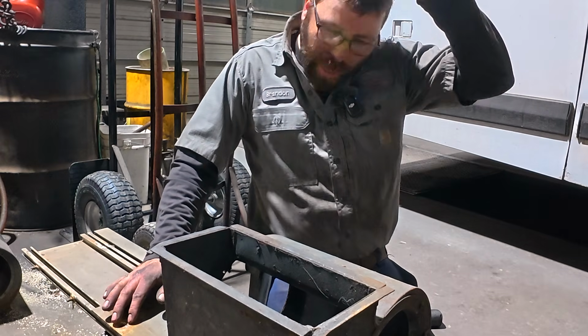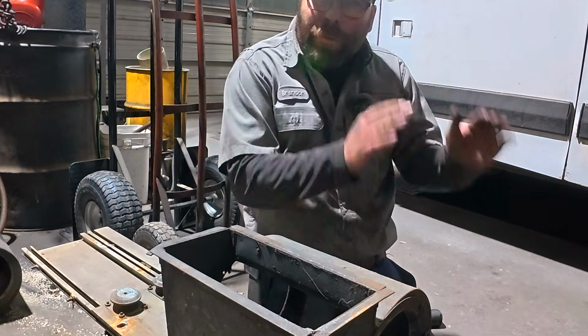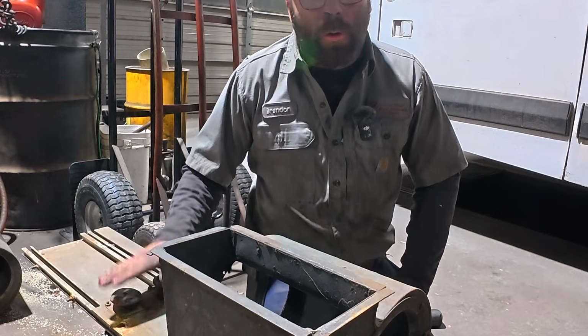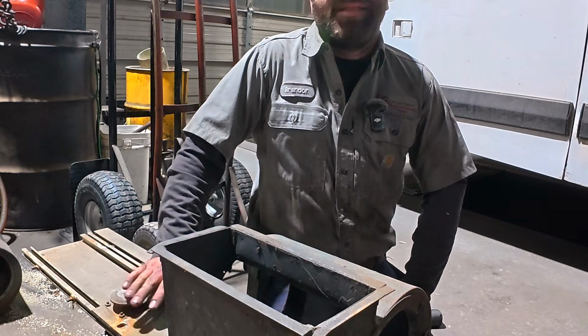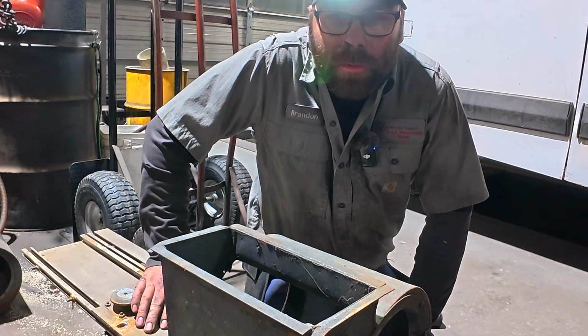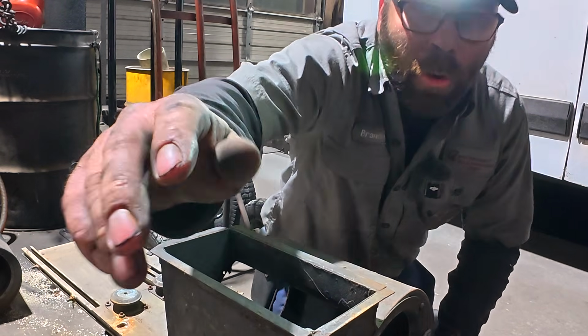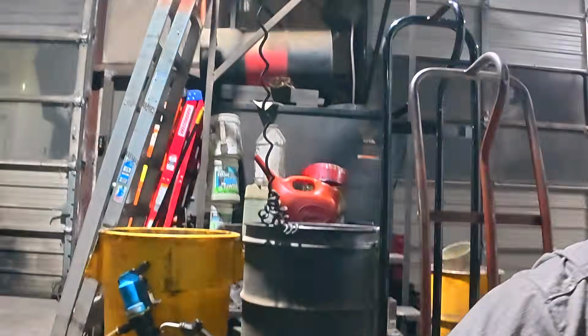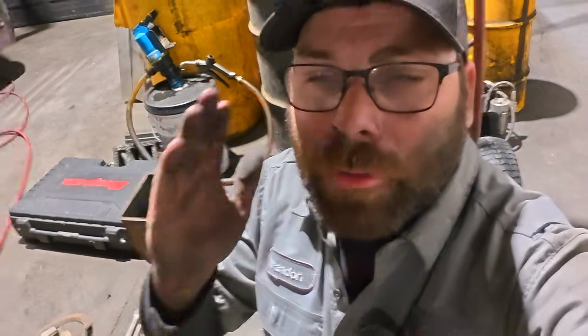It is very, very important that you put the squirrel cages on the correct way. I can't tell you how often buses come in here that other people have worked on and put the squirrel cages on incorrectly. I'd be richer than Donald Trump if I got $100 for every time I've had to pull the motor out, swap the two squirrel cages, take the right and put it on the left, and the left onto the right, to fix it after somebody else worked on it.